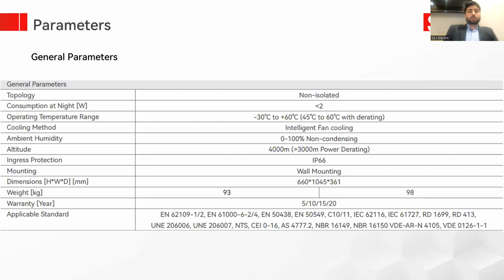General parameters: the topology is non-isolated, consumption at night is less than 2 watt, and the operating temperature range is minus 30 to 60 degrees Celsius. Cooling method is intelligent fan cooling, ambient humidity 0 to 100% non-condensing. Altitude is 4,000 meter and ingress protection is IP66. Mounting is wall mounting, dimensions 660 by 1045 by 361 depth in millimeters. Weight is 93 kg for 75 to 100 kilowatt and 98 kg for 110 to 125. Warranty is 5 years, extendable up to 20 years. Applicable standards are as per the market requirement. We have all of these types of standards and certifications.